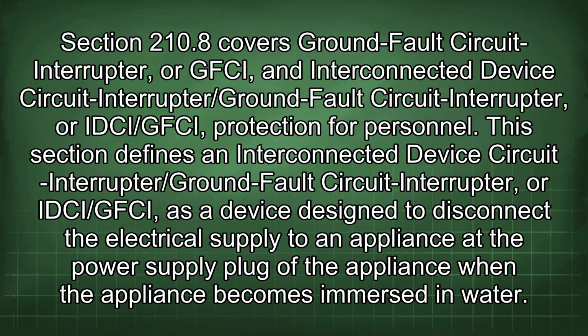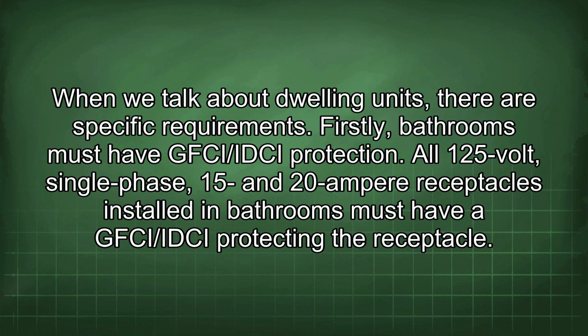Section 210.8 covers ground fault circuit interrupter, or GFCI, and interconnected device circuit interrupter / ground fault circuit interrupter, or IDCI/GFCI, protection for personnel. This section defines an IDCI/GFCI as a device designed to disconnect the electrical supply to an appliance at the power supply plug of the appliance when the appliance becomes immersed in water. When we talk about dwelling units, there are specific requirements.